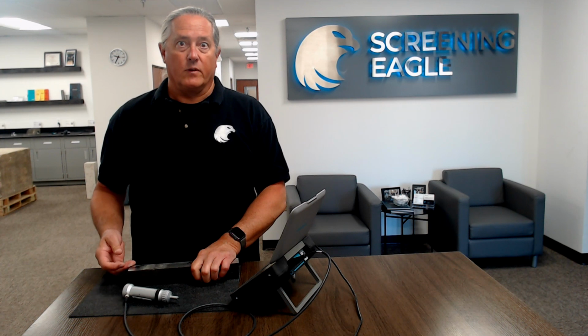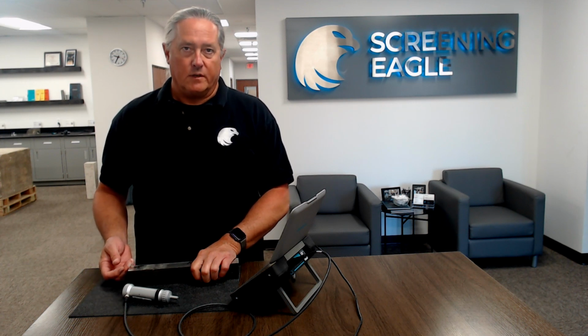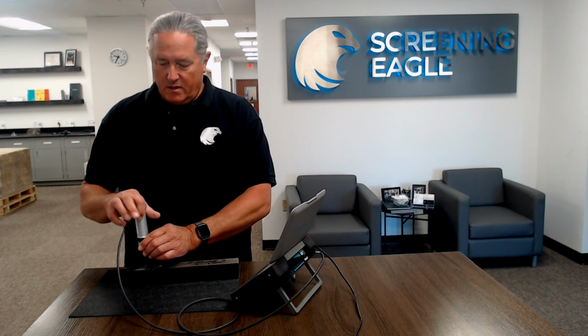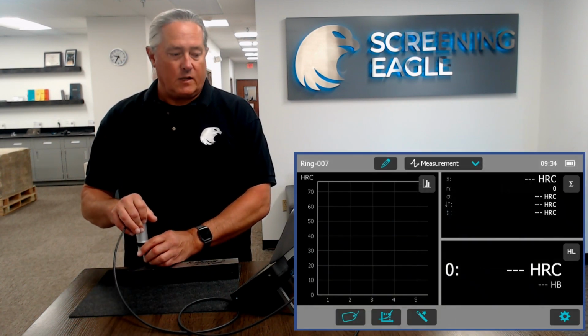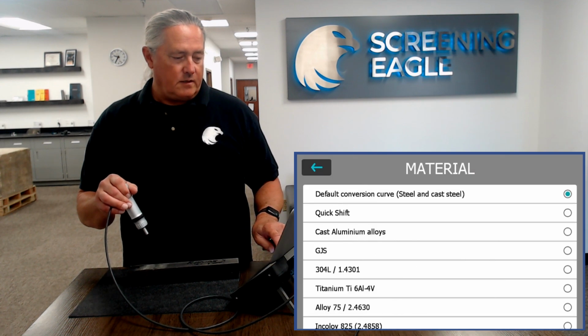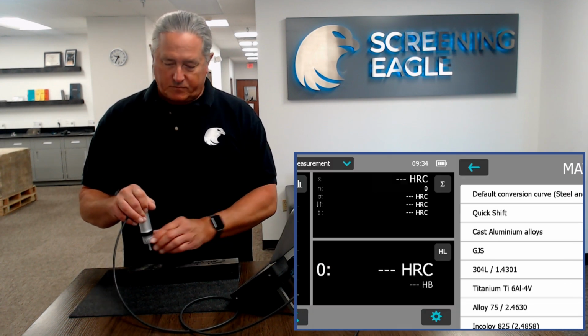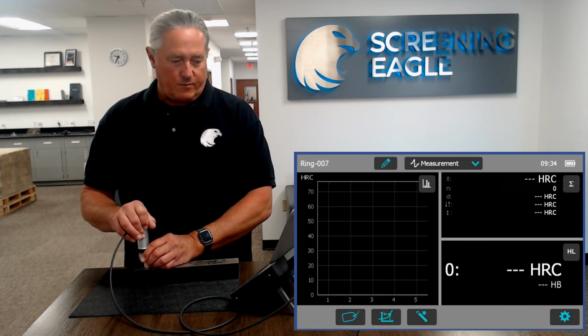Well, we have here an alloy that's been tested. It's marked 40 Rockwell C. It's just, as you can see, a sample of the material that we're going to be working with, and it was calibrated 40 Rockwell C on a benchtop laboratory instrument. So we can do a couple of different ways. First of all, let's check the default calibration. We're going to make sure we're in the default conversion curve group, and we're going to take a couple of readings.